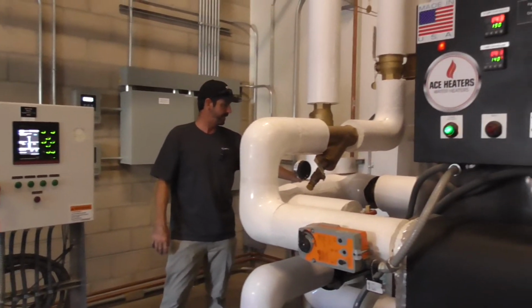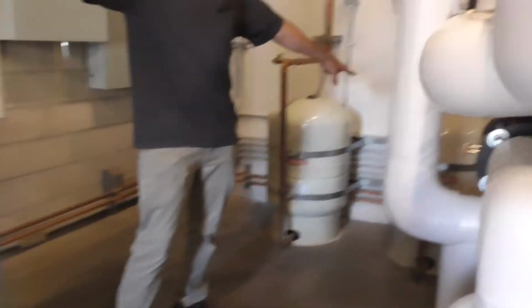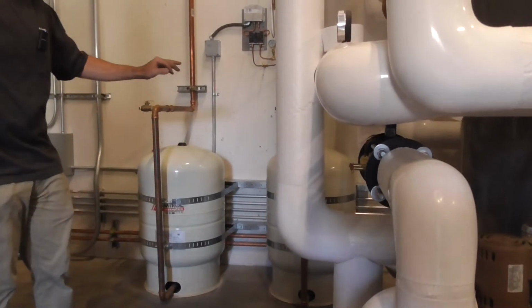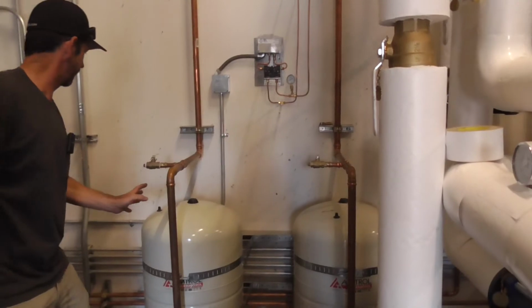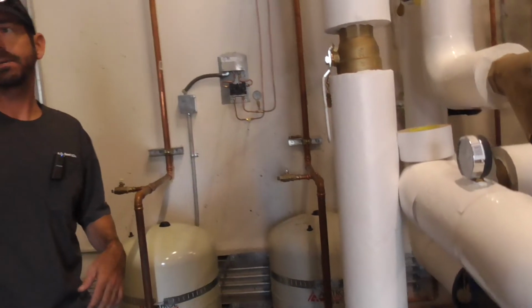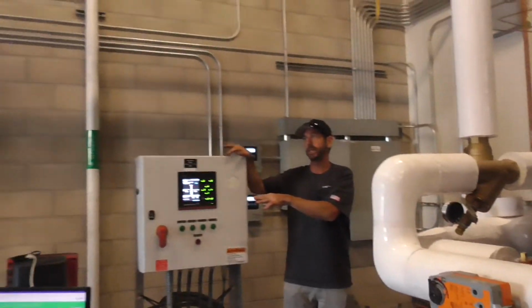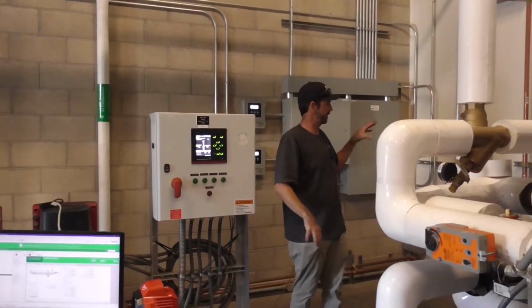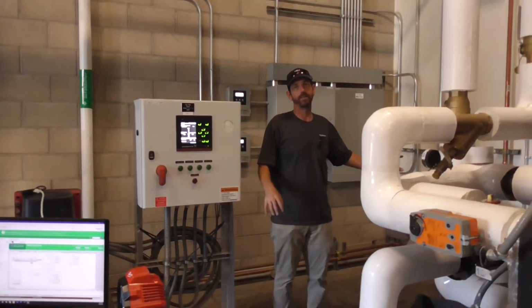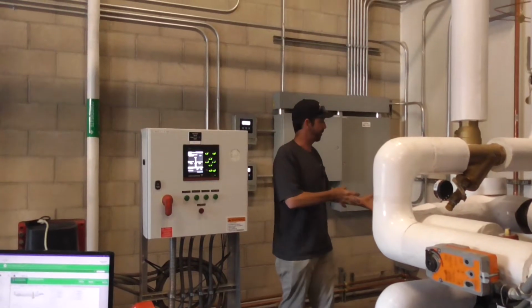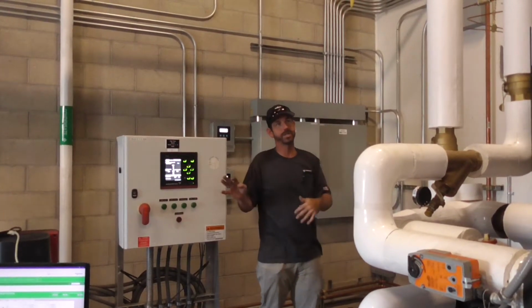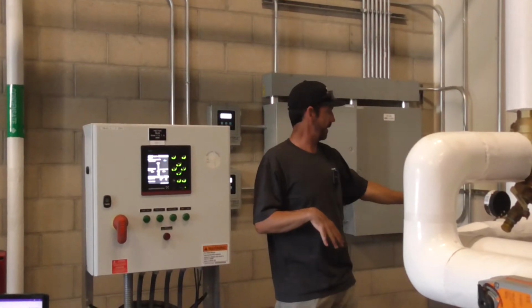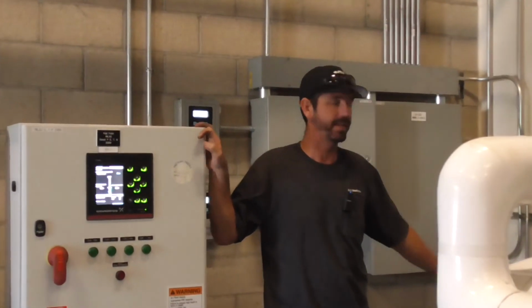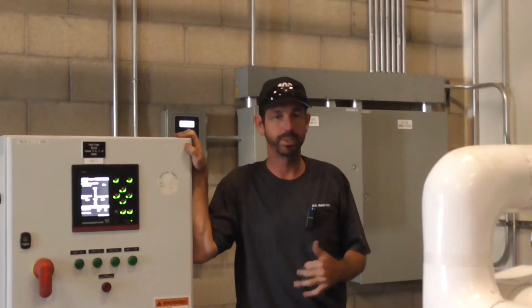The expansion tank on the right is set at 70 psi because that's our building set point. It's even because it's for the closed loop side of it. The expansion tank on the left is set at 50 pounds, which is 70% of this set point. That way, when this hits its set point, it pressurizes the tank and there's stored energy in that tank. So if someone opens one or two fixtures, the pressure in the tank comes out of the system instead of trying to turn on a pump. So the tank on the left is for the booster pump skid. We want 70% of your set point, which is 50 pounds.